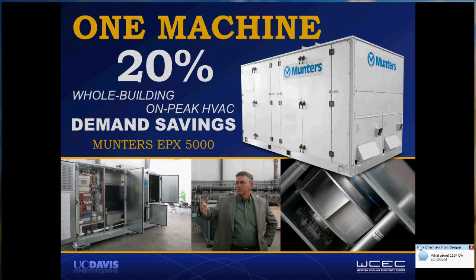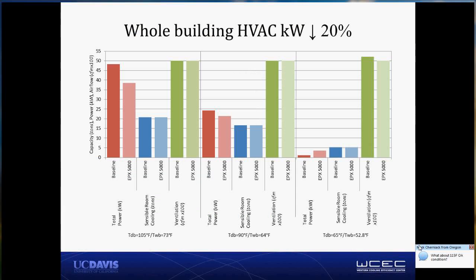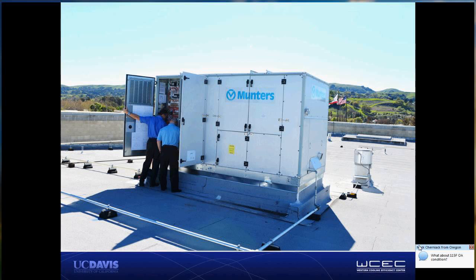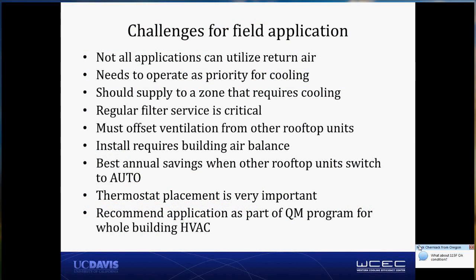And they don't have to carry their ventilation loads, and their room cooling loads are reduced because the additional cooling capacity from the DOAS system is carried across the zones in the store. So our scenario comparison suggests that adding this one piece of equipment onto a store would achieve 20% whole building peak demand savings. Which is exciting, pretty significant for needing only one system to do it. Skip through that, and we're running a field test in San Ramon on a grocery store. We'll have results from that, we expect, by the end of the summer season.